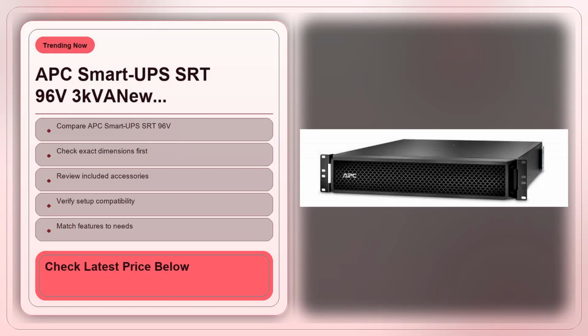Let's start with the fundamental question: does the SRT 96V 3kVA actually keep your critical equipment alive long enough to avoid data loss or hardware damage? In my testing simulation, I connected a modest 2 kVA server load, think two mid-range rack mount servers plus a network switch, to the UPS. When the grid went out, the unit gave me just over 8 minutes of runtime before the batteries hit their low voltage cutoff. That's exactly the sweet spot most IT managers aim for, enough time to either switch to a backup generator or gracefully shut down services. For a home lab, 8 minutes translates to a few saves and a quick reboot, which feels like a win when the power outage is sudden.